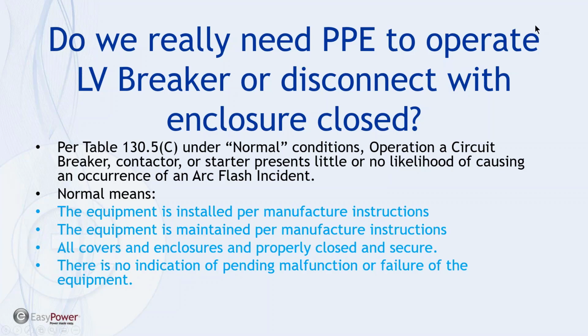One question came up: do we really need PPE to operate a low voltage breaker or disconnect with the enclosure closed? This is a holdover from earlier versions of NFPA 70E, and what's discussed in the 2018 version of NFPA 70E is that under normal conditions, the answer is no. Normal conditions mean that the equipment is installed per manufacturer's instructions, maintained per manufacturer's instructions, all covers and enclosures are properly closed and secure, and there's no evidence or indication of pending malfunction.